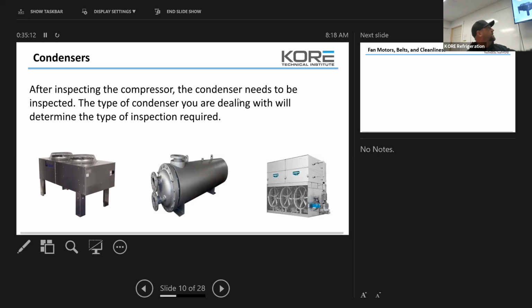Even in these air-cooled, if you're dealing with an adiabatic condenser, you're going to see air-cooled condensers now with wet pads as a pre-cooler. Like up at Trader Joe's, have you guys seen the one at Trader Joe's in Orem? That's a Trillium condenser. That's actually an air-cooled condenser with a wet pad pre-cooler on it. They call that an adiabatic gas cooler because you're using CO2 on it. But we have Costcos in Colorado that have them. Because these use pads, you might see what looks like a water-cooled condenser, but it's an air-cooled condenser with pre-cooler pads.